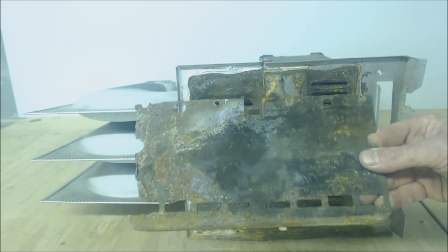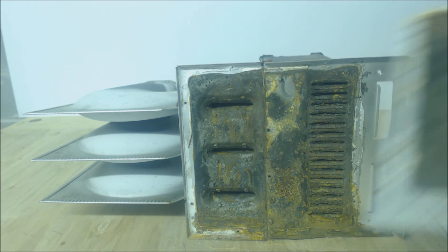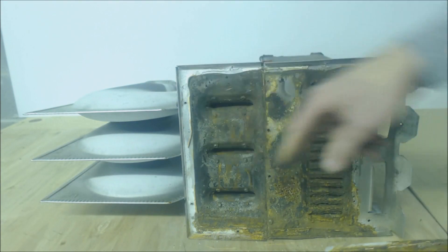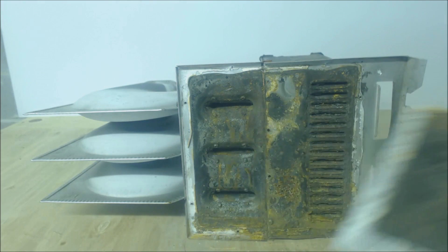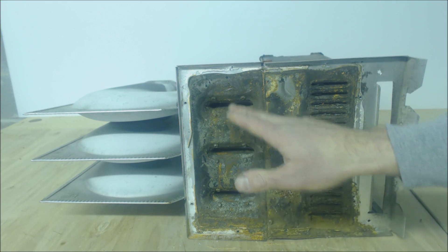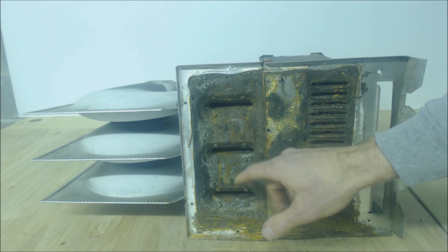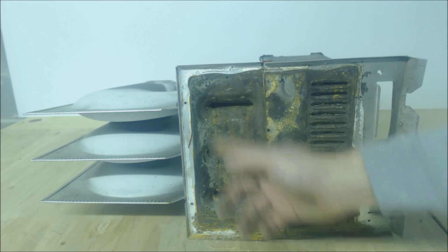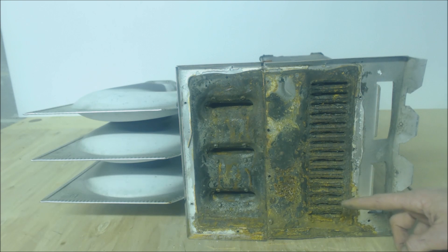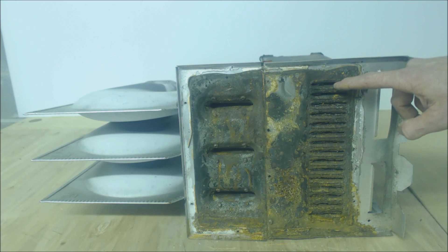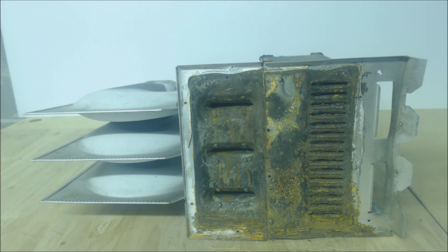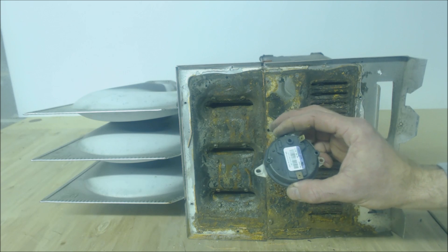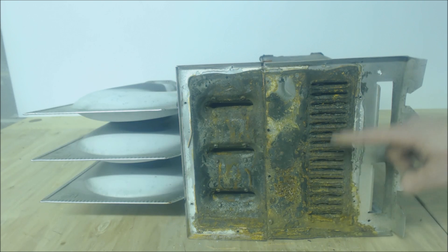I'm going to switch this around so you can see what the back looks like. You have your plate right here on the inside. Under this plate holds all the exhaust gases in with the gasket that runs around the perimeter. This is pretty rusted, but it's still in good enough shape to hold all the exhaust gases. This over here is your problem area. This side is still open enough to have the pressure switch read a negative vacuum when the inducer motor is pulling. But look over here - this is actually clogged solid.